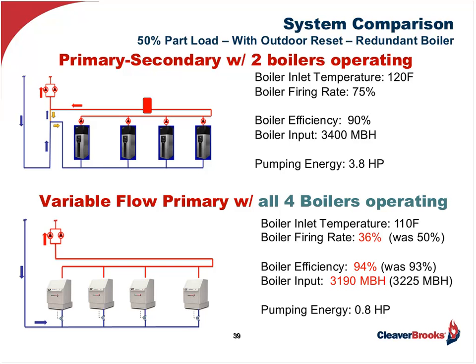One other scenario to remember, quite often as designers we add an additional boiler for redundancy so that if one boiler fails, we don't lose any heating capacity. Now with a primary-secondary arrangement, that fourth boiler doesn't really do you any good. It just sits there until it's needed. Because as you've seen, you really want to match the flow rate as closely as possible to your system rate. So at 50% part load, you would only run 2 boilers. And you'd have 1 boiler sitting at standby as well as the standby boiler.